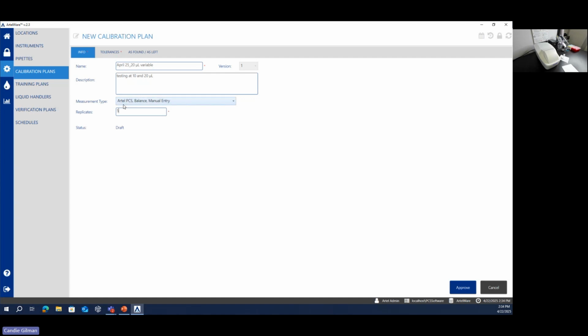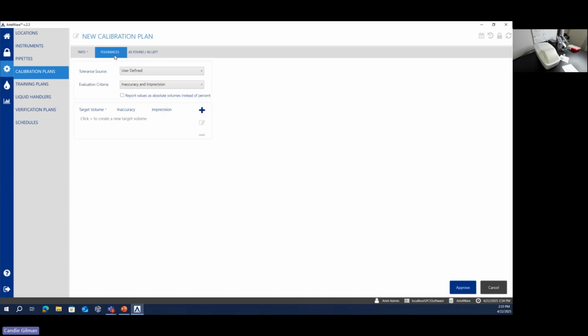So from here, now that I've defined the number of replicates, I now need to define my tolerances. What are the volumes that I'm testing at, and what are pass or fail? Now, the tolerance sources, I just wanted to show you real quick. You have a few selections for your tolerance source. You can choose ISO 8655 tolerances. They updated their tolerances in 2022. You could choose your own tolerances. You could choose pipette manufacturer tolerances.